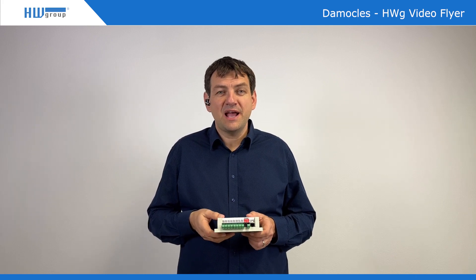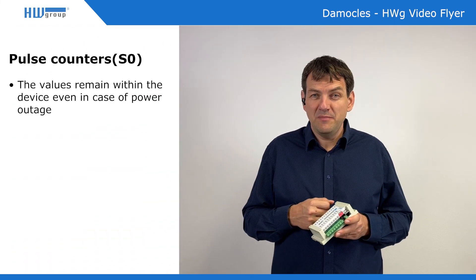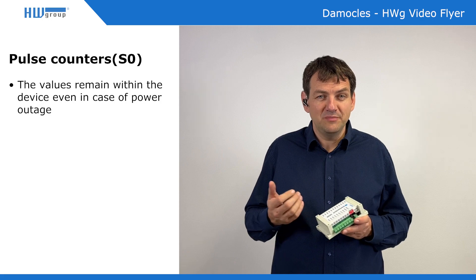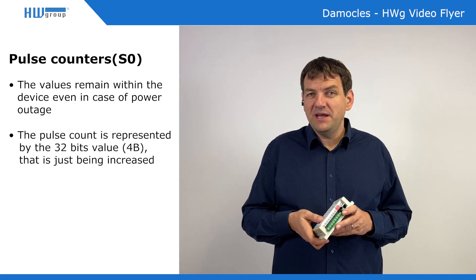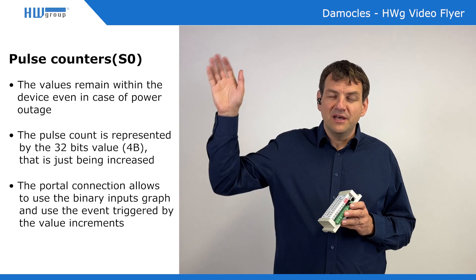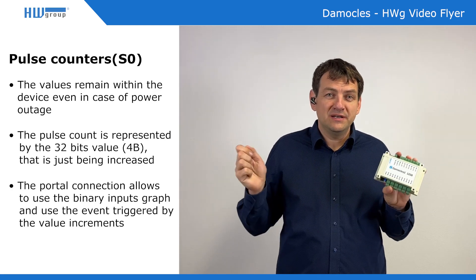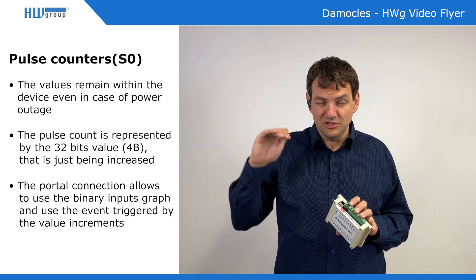One of the nice features of the Damocles is that on the digital inputs there are counters. So you can connect whatever is generating pulses — it can even be a mechanical counter of a water meter or something like that, where each pulse means something. There is a 4-byte counter and the counter value only increases, so even if you disconnect power and reconnect, the counter is still just an increasing number.